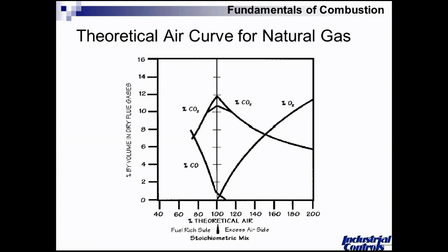Not shown on this graph but equally real is that when we have mechanical problems with the burner, firing head issues, parts that are burned or missing, you'll find that as you set your fuel air ratio, you'll not be able to achieve low levels of carbon monoxide. We're bringing a fuel envelope to play and bringing air potentially around it. We're not busting that fuel envelope up and allowing intimate mixing before we go into our combustion region on a burner. So what we want to do is look at this on a regular basis and look for trends, changes that might be indicative of mechanical changes in the burner itself.